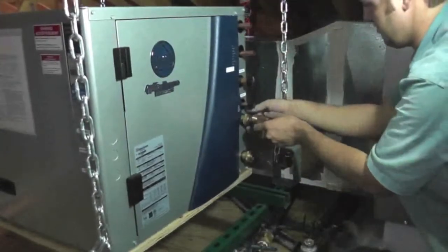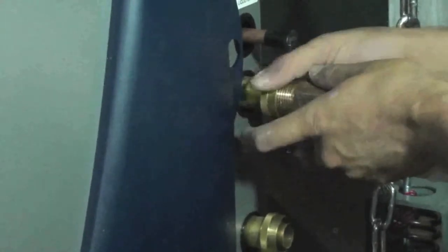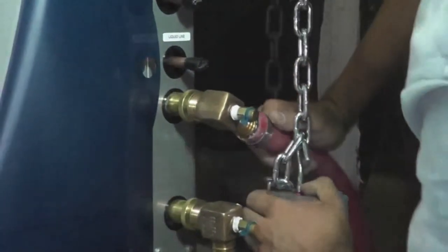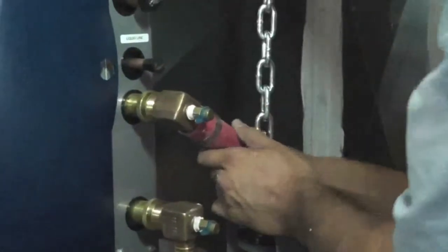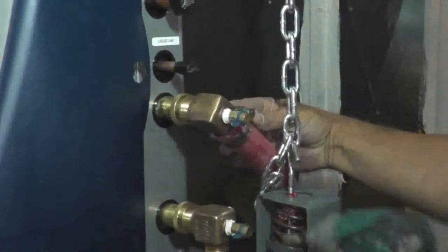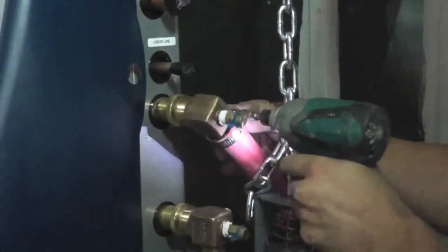Wendell is connecting the final hose fittings here for a five-ton WaterFurnace geothermal system in Lewisville, Texas. He is working with his team removing a failed heating and air conditioning system and replacing it with a premium ultra-high efficiency water source geothermal heat pump. He is taking special care to connect each fitting well, taking the time to assure each joint is leak-free and will stay that way.